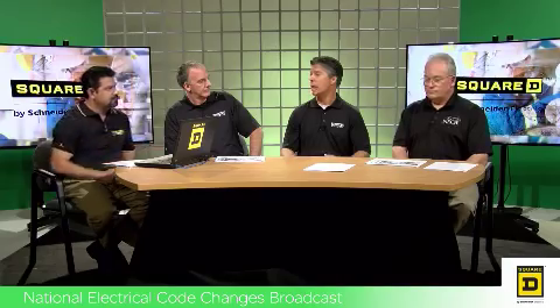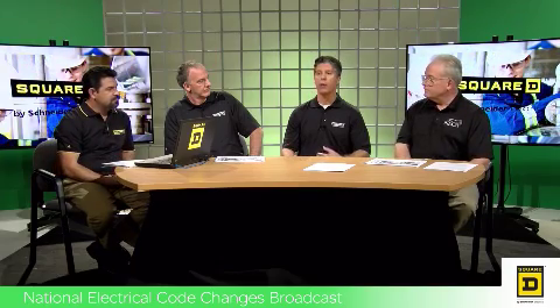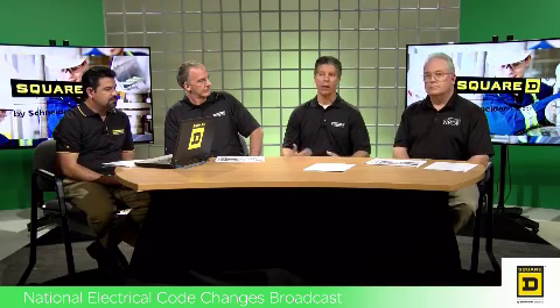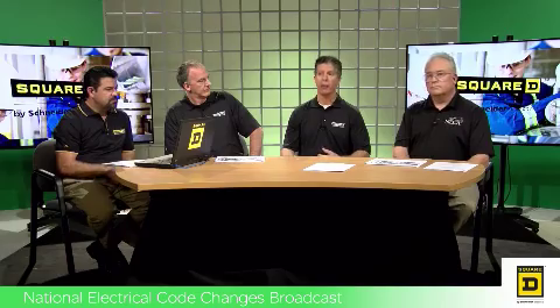And it allowed you to lower your energy load calculations for lighting loads. Now a new exception's added in the 2017 that goes a step further. If you have it calculated based on a lighting density, you can there reduce by 1 VA per square foot for banks, office buildings, and facilities like that. So we're seeing another area where the code is taking into account your energy efficiency gains by following your adopted energy codes. And I think this makes sense going forward as the buildings will have less infrastructure, but they have a less load as well.